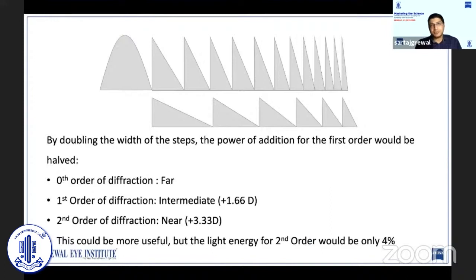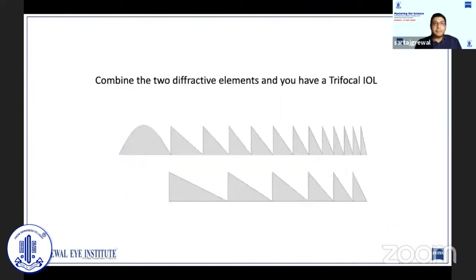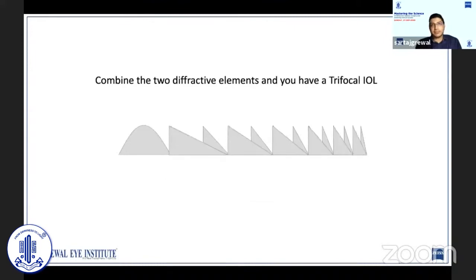However, the light energy would be only 4%, making the images too dim to be useful. So, if we create two different diffractive optics where the respective first orders provide near and intermediate vision separately, and adjust the height of the steps so that light energy is optimally distributed, then combine the two diffractive elements, you would actually have a trifocal IOL that corrects for near, intermediate, and distance, with light energy distribution that makes the vision comfortable at all these distances.